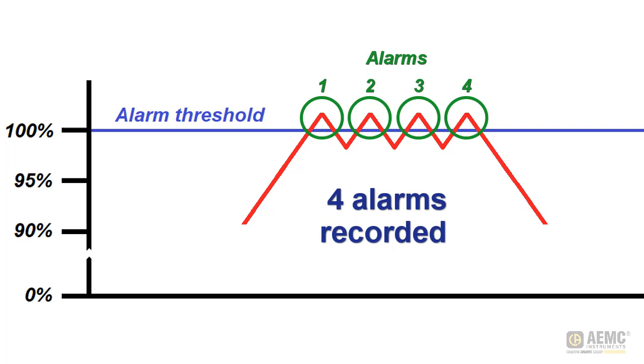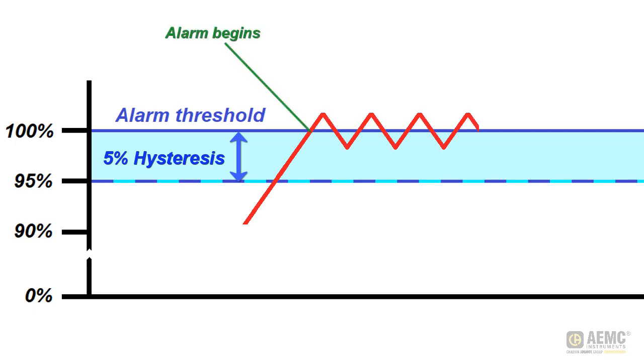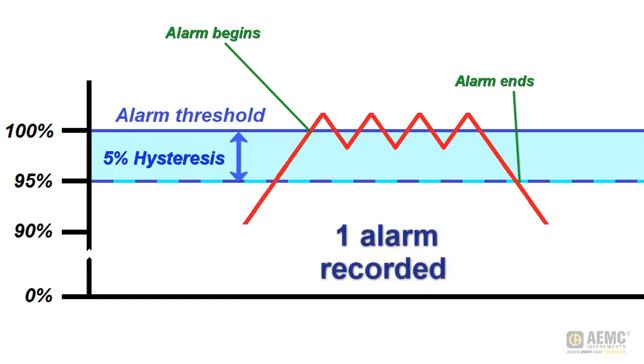Hysteresis filters out these alarms by introducing a measurement lag into the process. In our example, if we set hysteresis to 5%, an alarm will remain active until the measurement falls 5% below the trigger threshold. This also applies to minimum alarms — if the threshold is passed, the alarm remains active until the measurement exceeds the threshold by the hysteresis percentage.